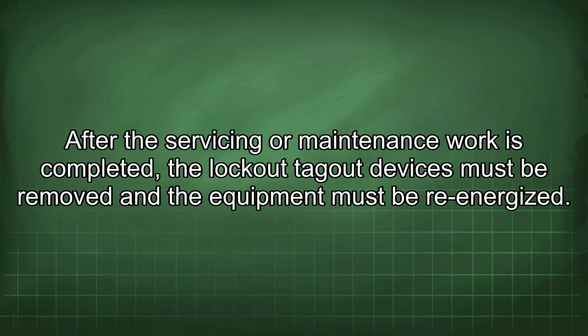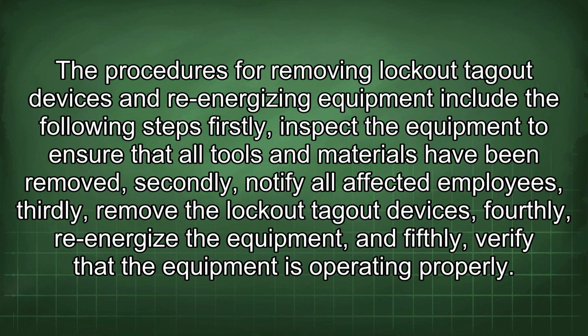After the servicing or maintenance work is completed, the Lockout Tagout devices must be removed and the equipment must be re-energized. The procedures for removing Lockout Tagout devices and re-energizing equipment include the following steps. Firstly, inspect the equipment to ensure that all tools and materials have been removed. Secondly, notify all affected employees. Thirdly, remove the Lockout Tagout devices. Fourthly, re-energize the equipment. And fifthly, verify that the equipment is operating properly.